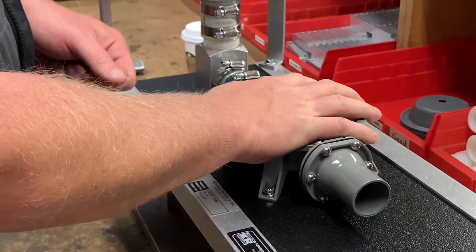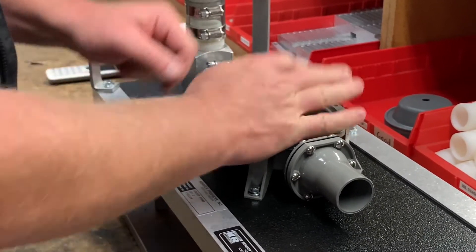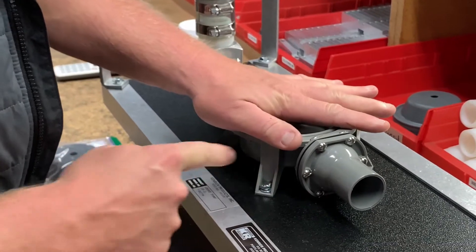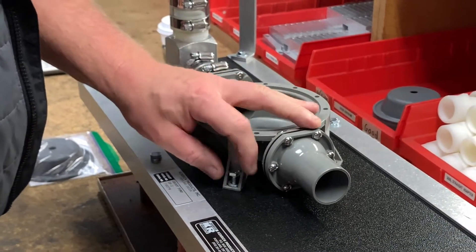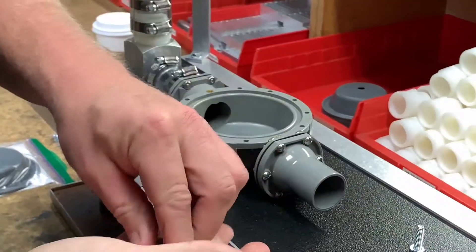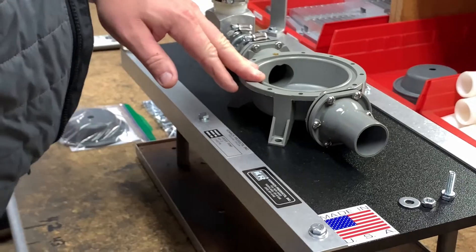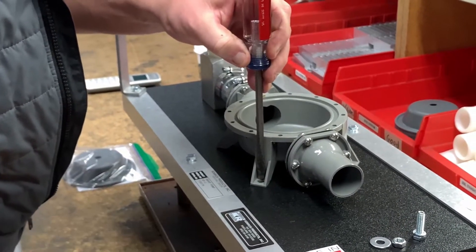To take your plastic pump body off from the base in order to change your flapper valve — for the sake of time I've already taken off three of the four one-inch cap screws that hold the pump body to the baseboard. You will have to remove all four. You'll have a lock washer, one-inch cap screw, flat washer, and a nut — this is where the 7/16 wrench comes in to loosen those up.